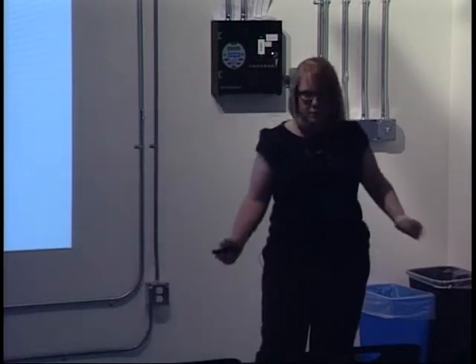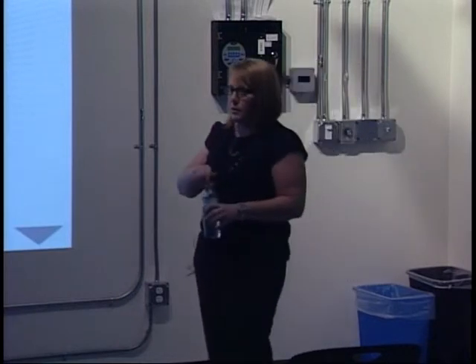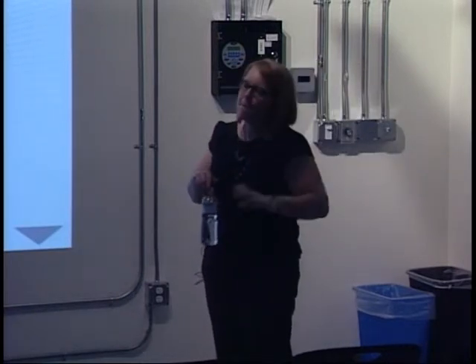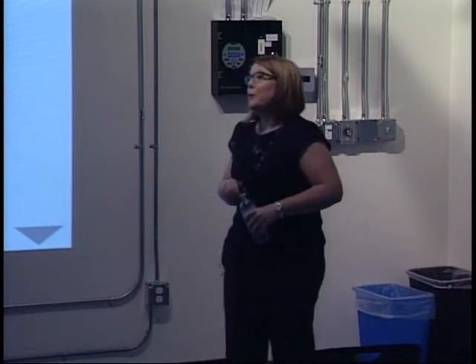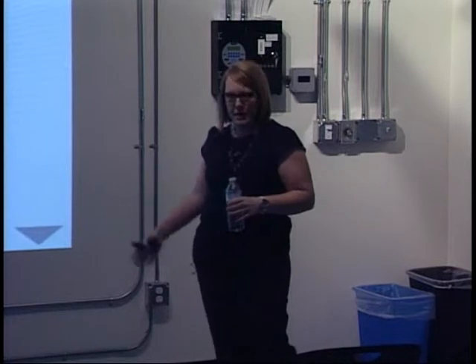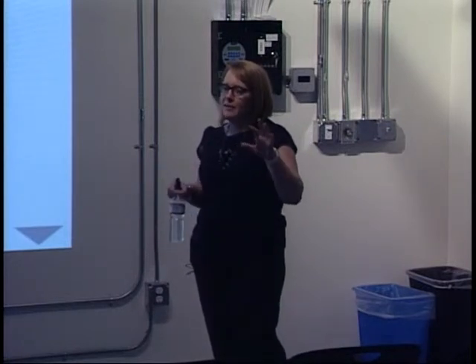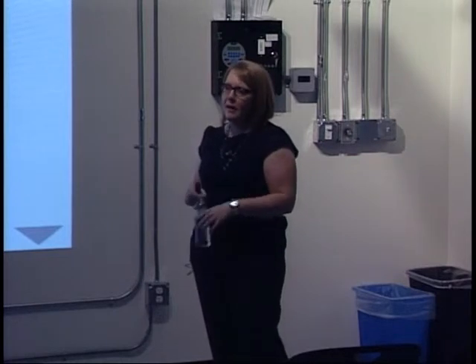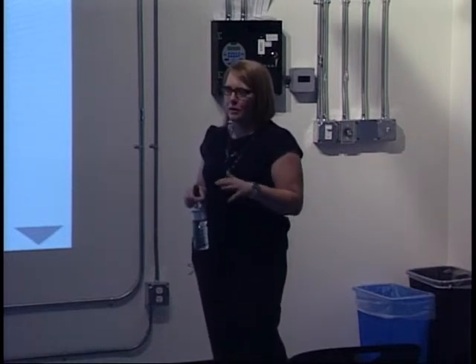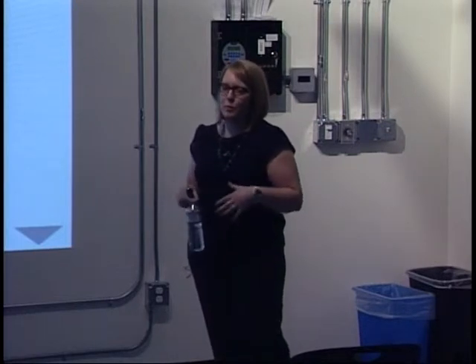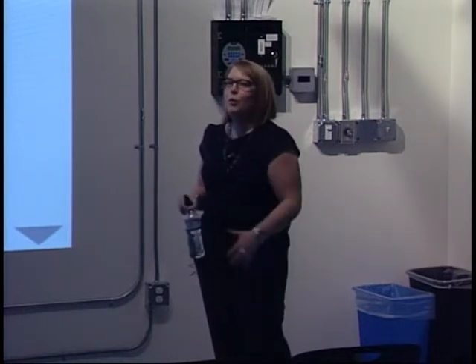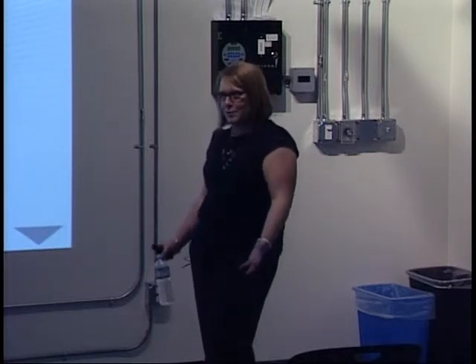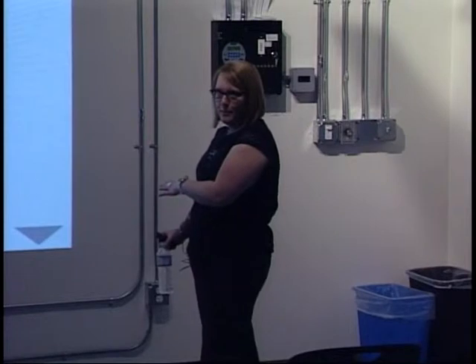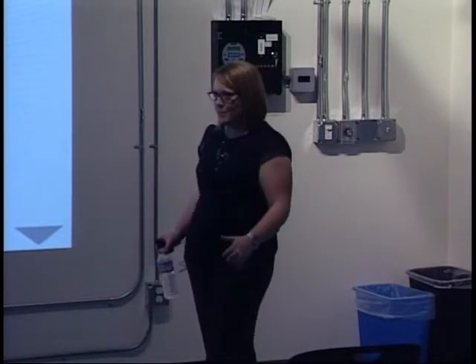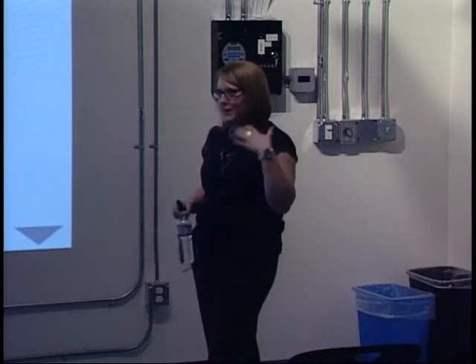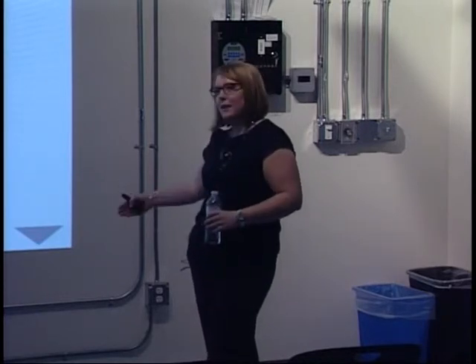Yeah. I can't remember, was the radiant system what you saw mostly in Europe, right? Right, so really ubiquitously, radiant heating panels are used for heating, and the cooling is actually taken care of in the air at a really low air change rate. So same as what we would be required to do by code here, but they don't ramp it up. What we're required to do here is 4 air changes per hour when we do this kind of system. And in Europe, what you see is 4 air changes per hour with all the cooling that's needed in those 4 air changes, and then radiant heating at the window.